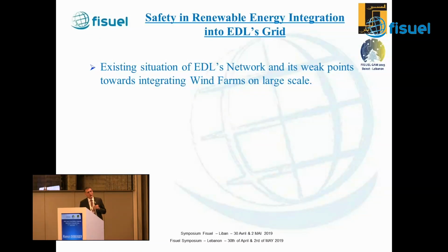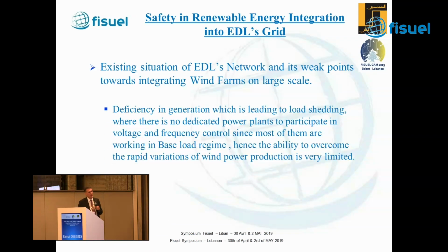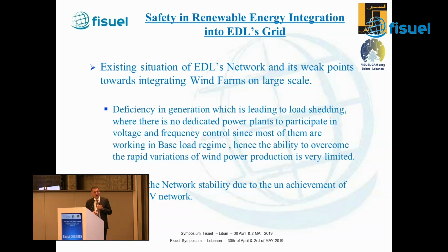The existing situation of EDL's network and its weak points towards integrating wind farms on a larger scale are because of, first, the deficiency in energy, which is leading to load shedding, where there are no dedicated power plants to participate in voltage and frequency control, since most of them are working in base load regime. Hence, the ability to overcome the rapid variations of wind power production is very limited. Second, the lack of network stability due to the non-completion of the 220 kilovolt network.